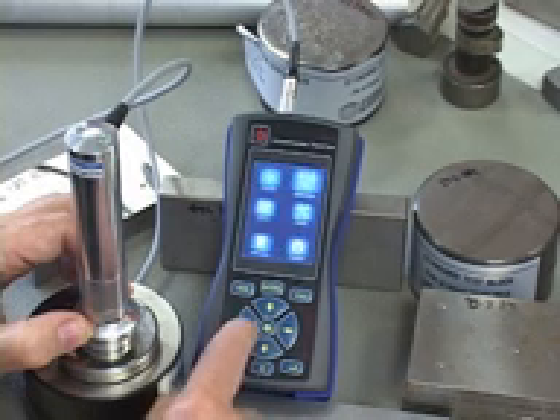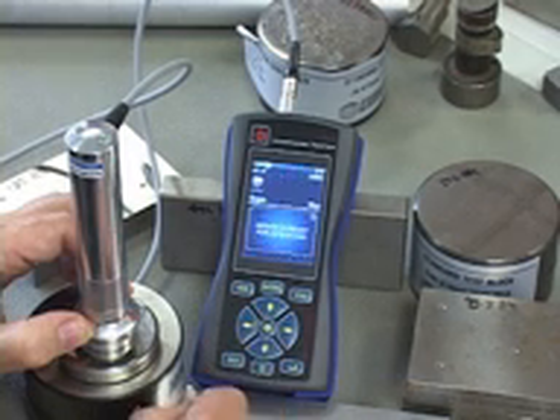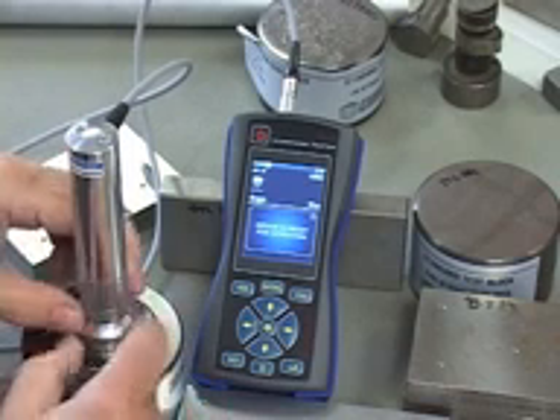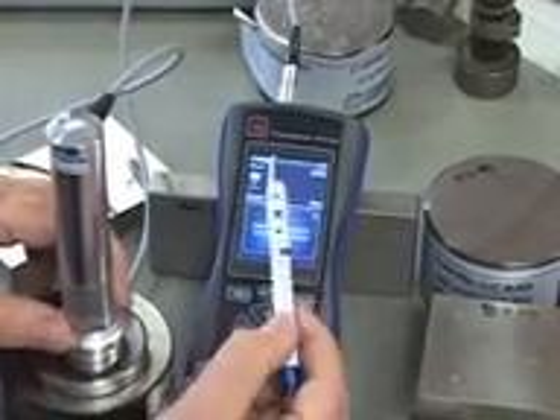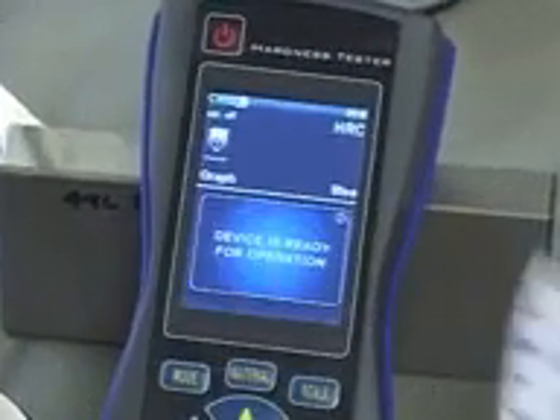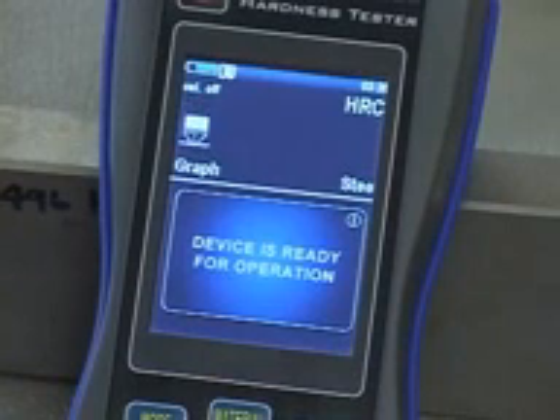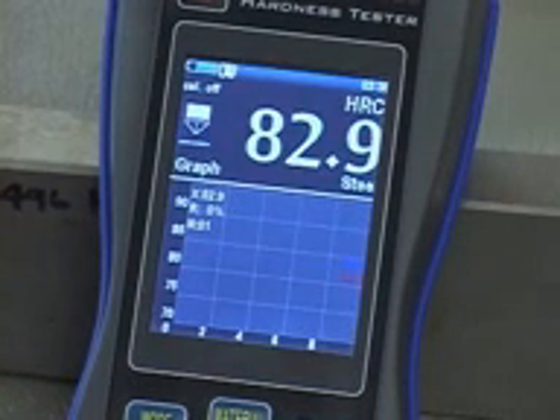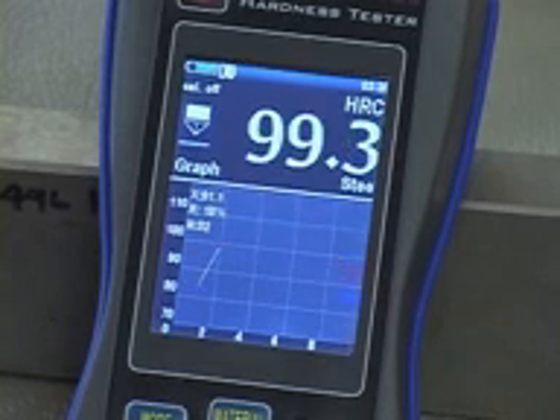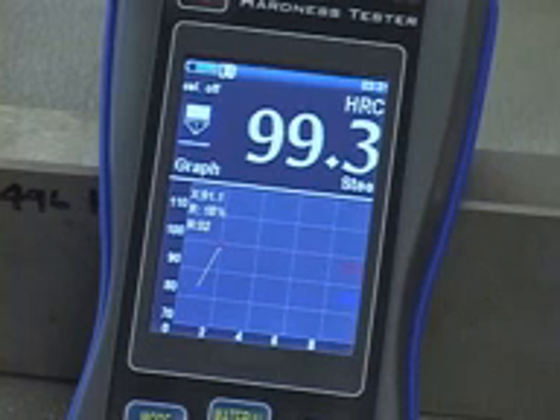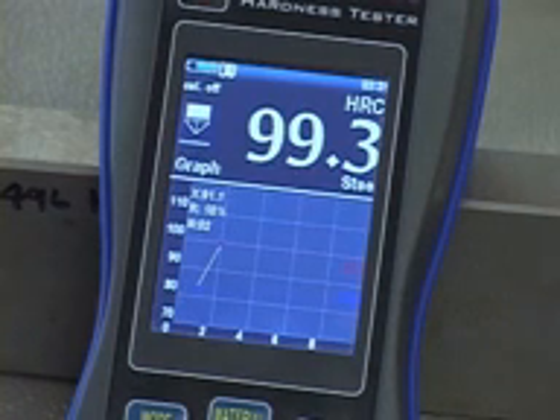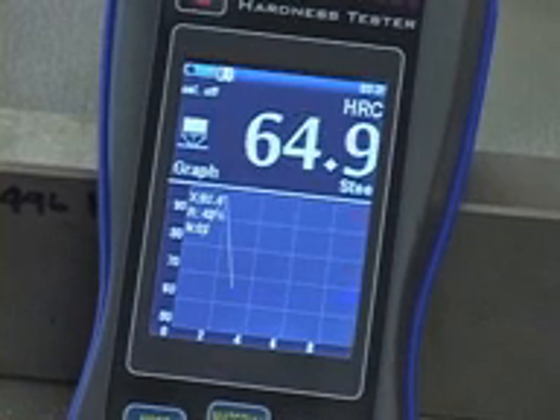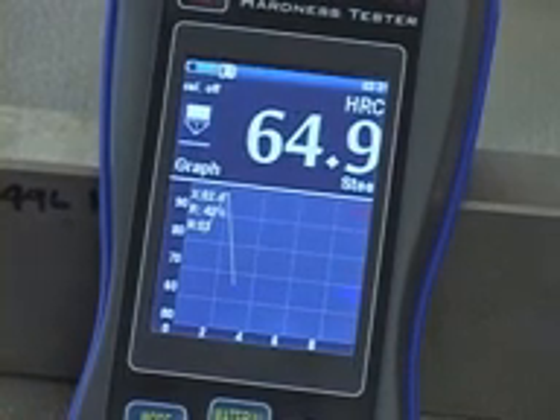So let's just go back out of here. I'm going to go to measuring and just show you now some tests. I'm just going to show you initially that this is a little icon that shows that the diamond tip has made contact with the part. But if you press down and you just make that contact without that second motion, you will get very, very wildly varying results, because what's happened is when the diamond tip contacts the part, it then sets the little coil inside to start the vibration of the rod to do the test. But because I haven't followed through with that second motion to press down to actually have the test done correctly with the correct load, in this case 12.5 pounds, I'm not getting an accurate result.